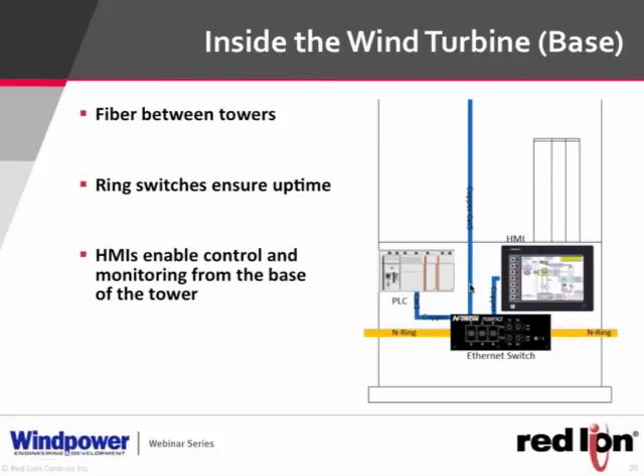A typical wind farm has turbines scattered across a landscape with long distances between them. Copper has a limitation of 328 feet, so fiber optic cables are used between turbines, while copper may be used inside the turbine itself. The diagram shows an Ethernet ring connecting all towers — each switch participates in the ring, and the ring provides redundant connectivity between towers.